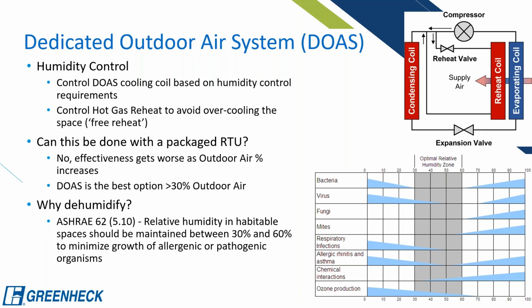So can this be done with the packaged rooftop unit? The answer is essentially no, because as you increase your requirement of ventilation air above 30%, you're gonna need a DOAS unit to do it effectively. And if you're wondering why would you even dehumidify, ASHRAE 62 states this pretty well, that habitable spaces need to be between 30% and 60% just because of mold growth, essentially. Bacteria, virus, fungus, everything, it fits really well into that 30 to 60%.